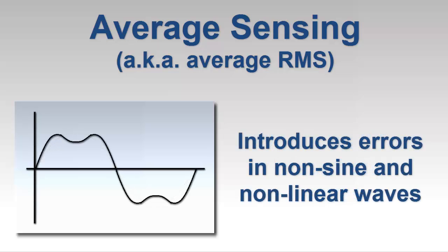Unfortunately, for other AC waveforms, such as square waves, this calculation can introduce significant inaccuracies. The equation can also be problematic when an AC waveform is nonlinear, as would be found in systems where the original or fundamental waveform is distorted by one or more harmonic waveforms. In these cases, we need to apply a method known as True RMS.